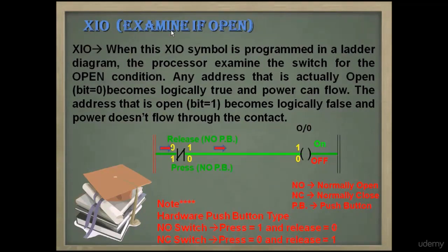XIO instruction stands for examine if open. When this XIO symbol is programmed in a ladder diagram, the processor examines the switch for the open condition. Any address that is actually open (bit=0) becomes logically true and power can flow. The address that is closed (bit=1) becomes logically false and power doesn't flow through the contact.